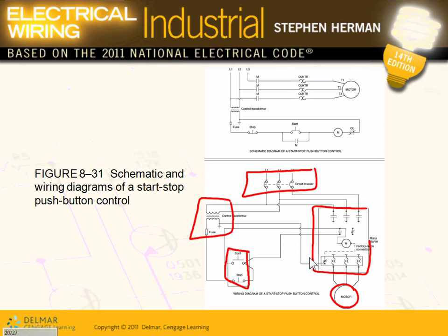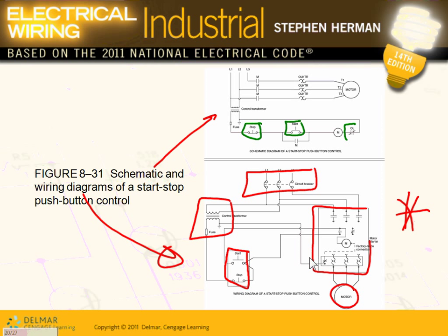The schematic diagram cares less about where the boxes are located — it just shows the control logic. In order to wire the system, you really need the wiring diagram. The schematic helps you understand the system. With the wiring diagram I can go wire right now; the schematic tells me to understand, but it may not tell me that multiple components shown separately are actually all in one box.